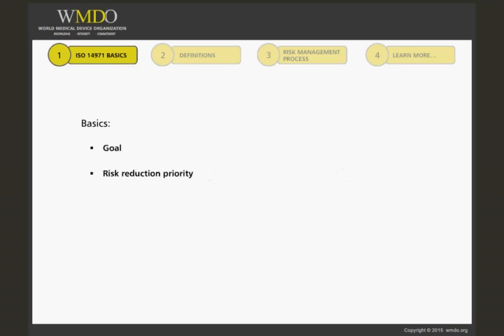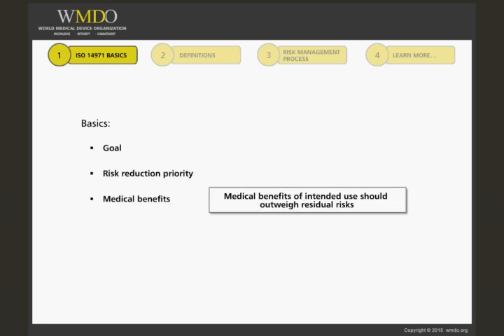As you can see, the standard doesn't ask that all risks should be reduced to zero. The bottom line is that medical benefits related to the intended use of your device should outweigh the residual risks.